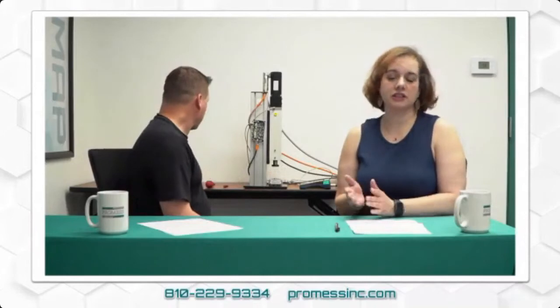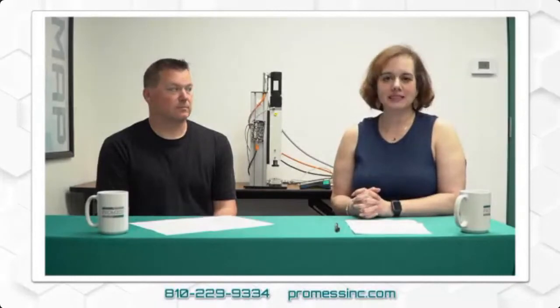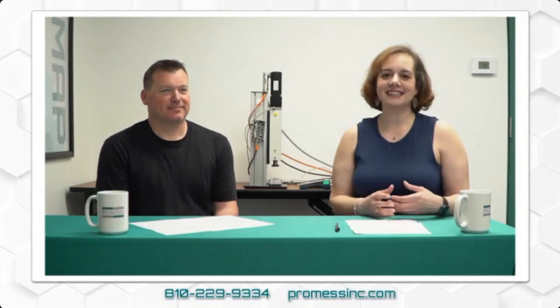For auto-calibration, you need to have the latest motion control software, which is the Ultra Pro software, along with the digital signal conditioner, which we refer to as a DSC, and then the Pro CM16, which is our calibration meter. The digital signal conditioner is the conditioner that our integrated load cell is already going to. You take the Pro CM16 and connect it to that DSC through a USB cable. The nice thing is that now you can just go into your Ultra Pro software and create a calibration program, which is going to look very similar to a production program, only it has additional steps that allow for handshaking between the controller and the DSC to let it know to take the values from the Pro CM16, do the check to see if it is within tolerance, and make any adjustments as necessary.